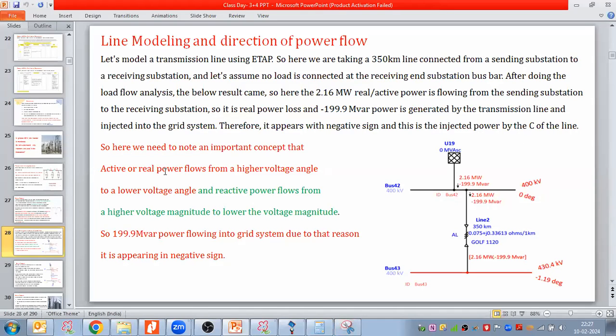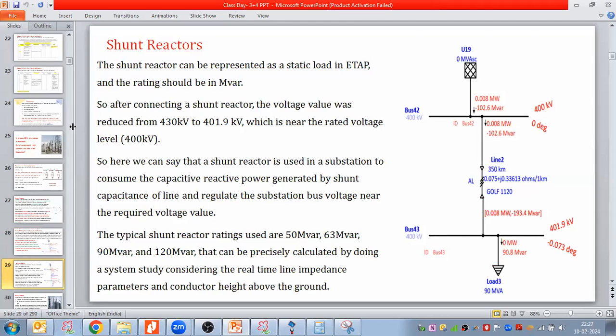So here we need to note an important concept: active or real power flows from higher voltage angle to lower voltage angle, and reactive power flows from higher voltage magnitude to lower voltage magnitude. So 199.9 MVAR power is flowing into the grid system. Due to that reason, it appears with a negative sign here and everywhere. Here, the shunt reactor can be represented as a static load in ETAP, and the rating should be in MVAR. After connecting a shunt reactor, the voltage value was reduced from 430 kV to 400 kV, which is near to the rated voltage level.